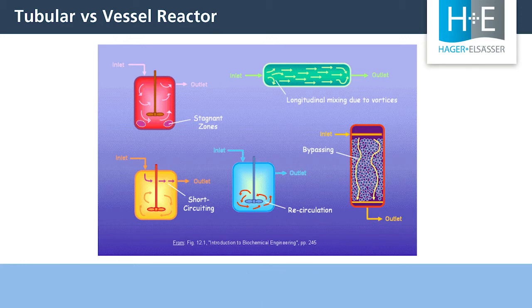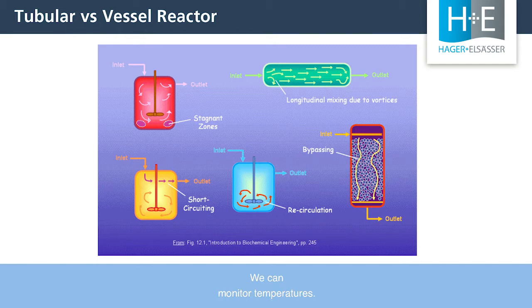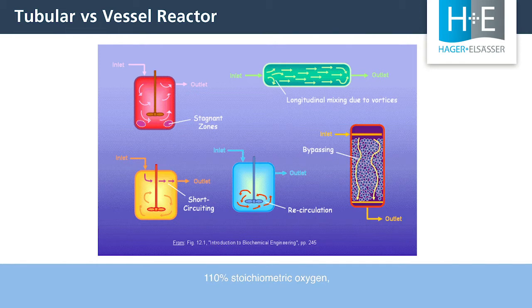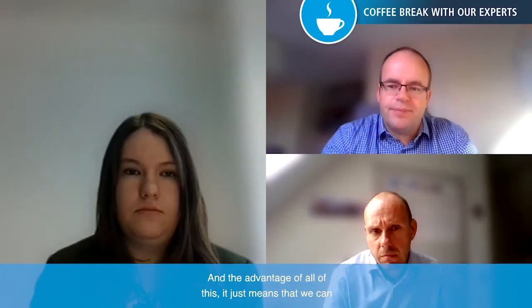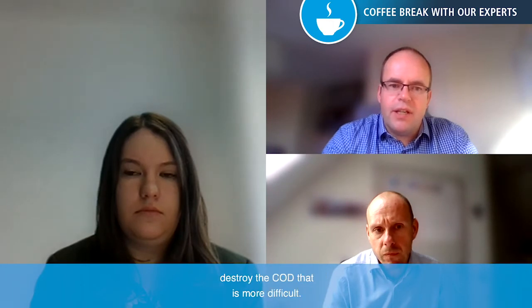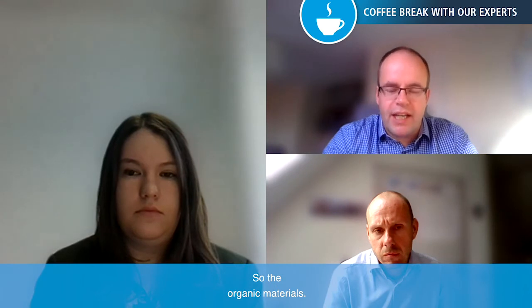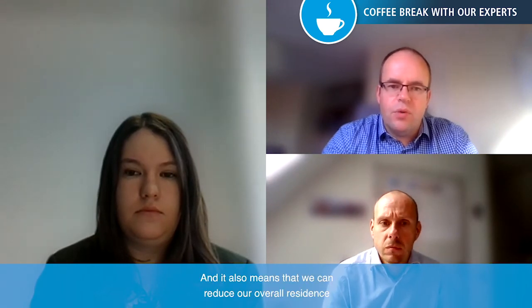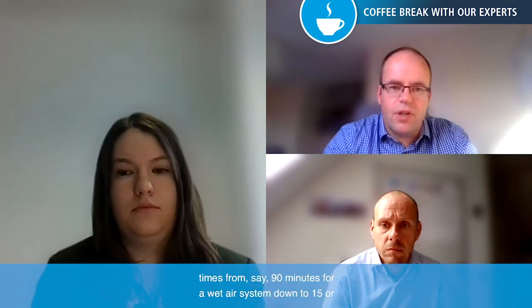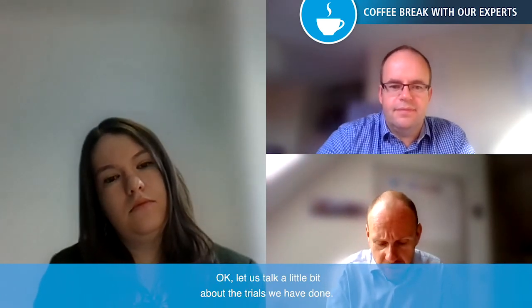The tubular reactor also allows us to break the reaction into stages. Aquacrytox allows injection of oxygen in three separate locations along the reactor, so we can optimize the oxidation process, monitor temperatures, and optimize the amount of oxygen injected. For Aquacrytox, we inject around 110% stoichiometric oxygen, whereas a conventional wet air oxidation package may use up to 300% oxygen. This means we can destroy more difficult COD compounds and reduce overall residence times from around 90 minutes for a wet air oxidation system down to 15 or even 12 minutes for Aquacrytox.